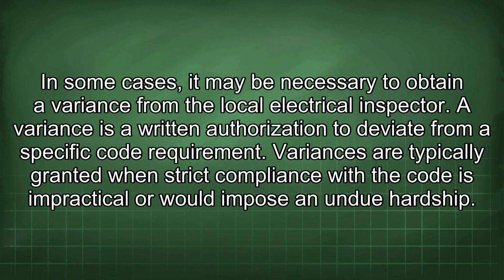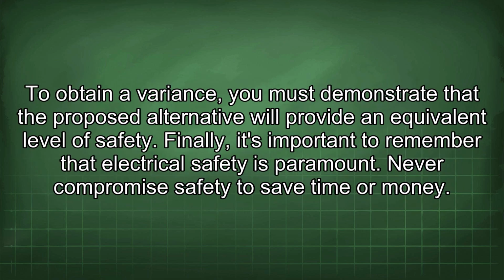In some cases, it may be necessary to obtain a variance from the local electrical inspector. A variance is a written authorization to deviate from a specific code requirement. Variances are typically granted when strict compliance with the code is impractical or would impose an undue hardship. To obtain a variance, you must demonstrate that the proposed alternative will provide an equivalent level of safety.